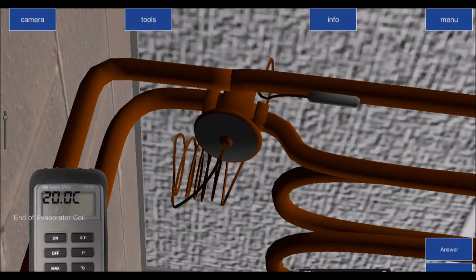This is your high pressure, high temperature liquid going into your thermostatic expansion valve, pressure drop created, and here we've got low pressure, low temperature liquid entering into your evaporator.